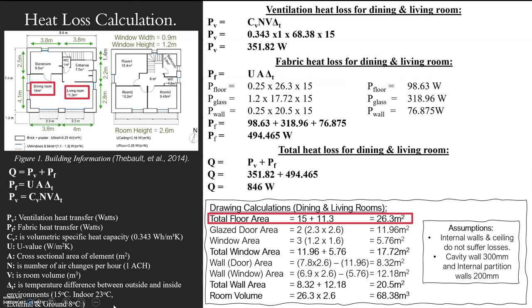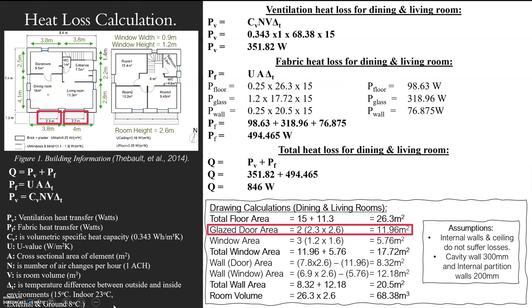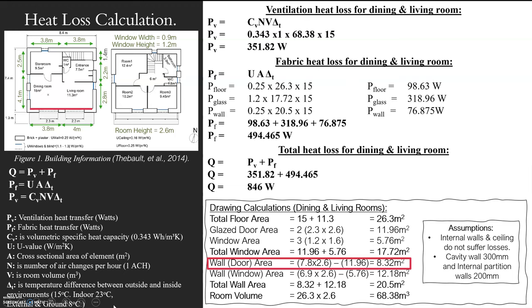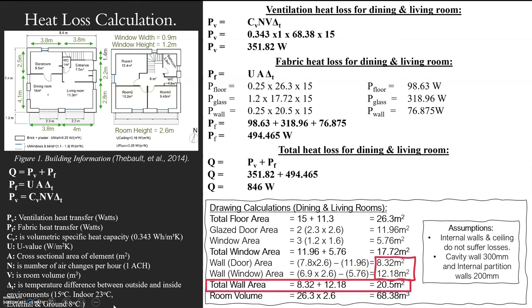Moving on to areas. I look at my floor area because I need to know how much heat is going to transfer through the floor to the ground. I look at my glazed doors and windows together because they share the same U-value. Then I look at my walls — the ones that the doors are on and the ones that the windows are on — to find how much actual wall area heat is going through. And my volume is specifically for the ventilation heat loss, so I need to know the volume of my space.